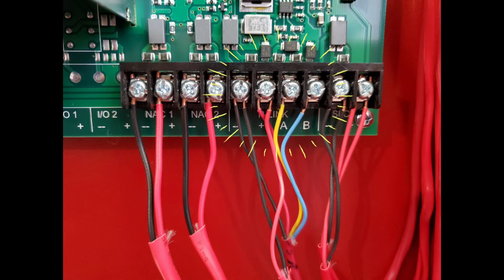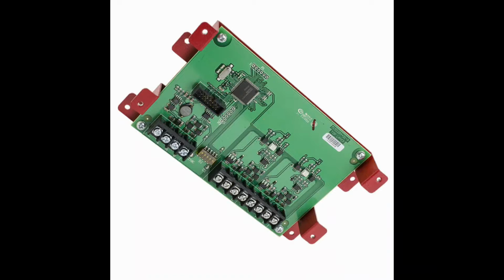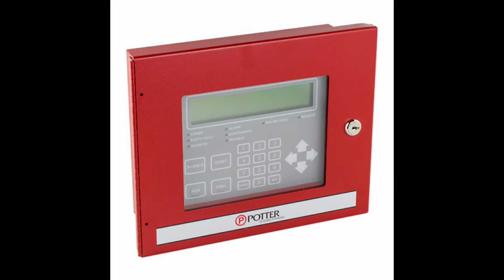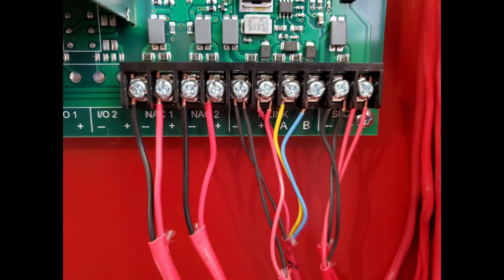Next, let's take a look at the P-Link terminals. The P-Link terminal is for an additional card that connects to the panel that gives it an extra ability. For example, this card has extra SLC and P-Link terminals, or it can give you an annunciator, which is essentially a mini panel that goes towards the front of the building so the fire department knows exactly what's going on when they enter.